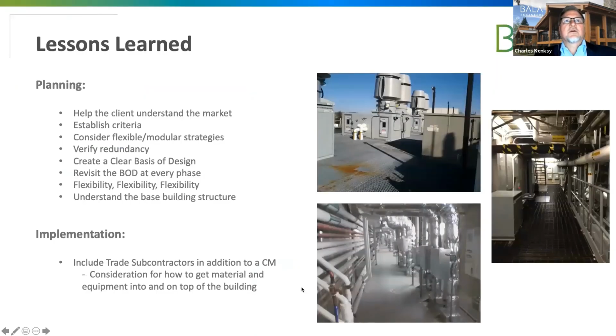On the roof here you've got your strobic fan array on top, and on the bottom, this is what we'll call a utility corridor. The lab is on the left-hand side, you see the rack of piping for the utilities, and the VAV boxes on the right, some exhaust, some supply. Using a piece of the floor for utility space, given the floor-to-floor height wasn't enough, is another viable option for fitting everything into a low floor-to-floor height.